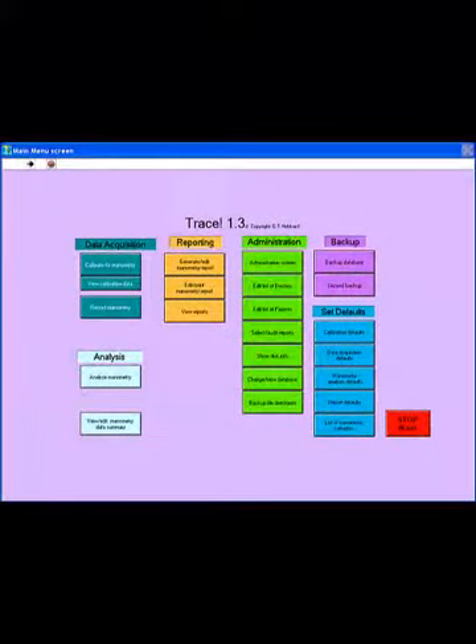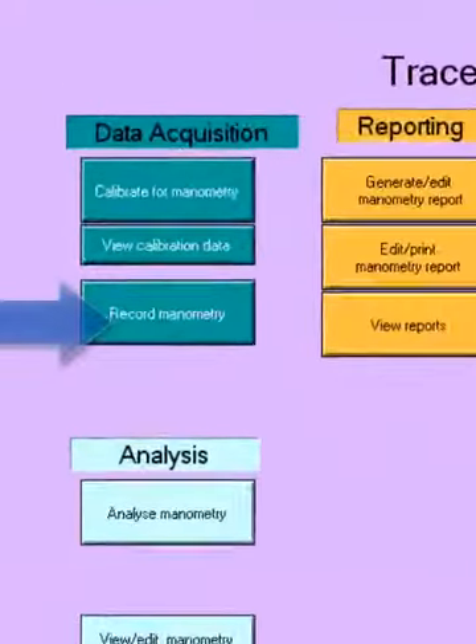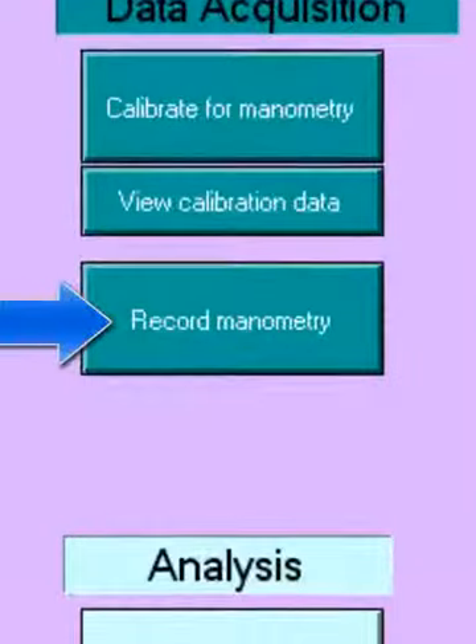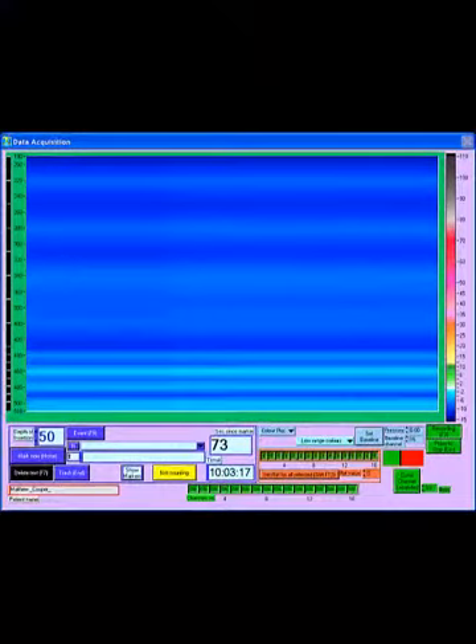To check that the catheter is functioning correctly and to remove the pressures generated by perfusing water through the lumina of the catheter, start the software and a data acquisition. Select the appropriate calibration and patient, and the recording screen will come up looking similar to this one. Pressures will differ between channels as the pressures required to perfuse each channel differ. In general, the pressures in the lower channels will be more positive as they have a longer fluid path and hence a higher resistance.